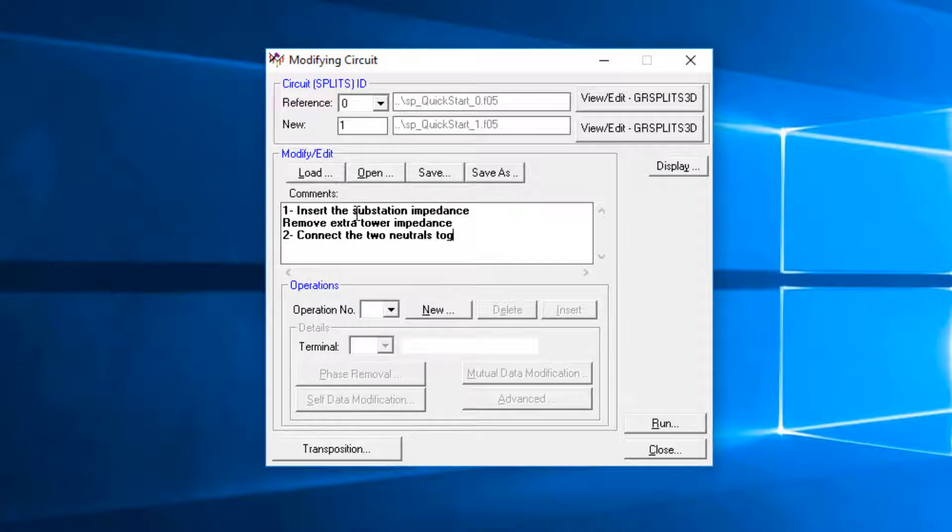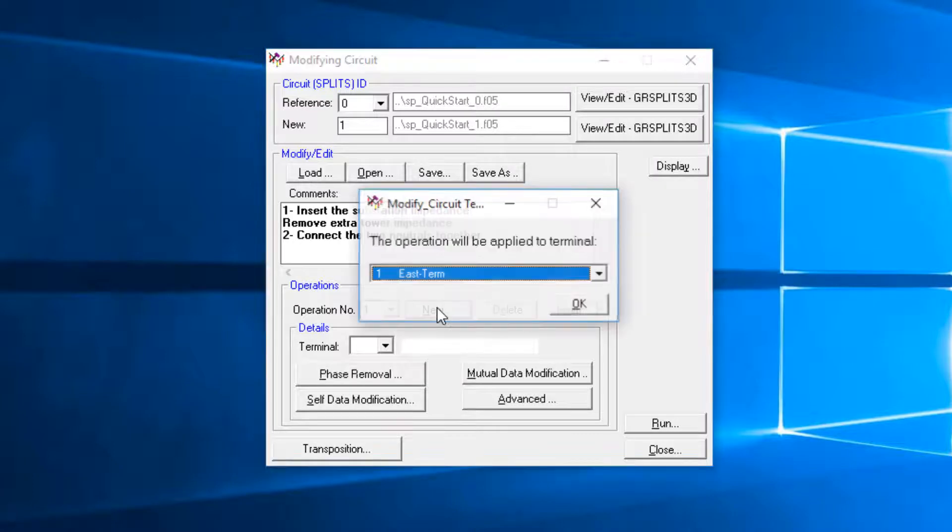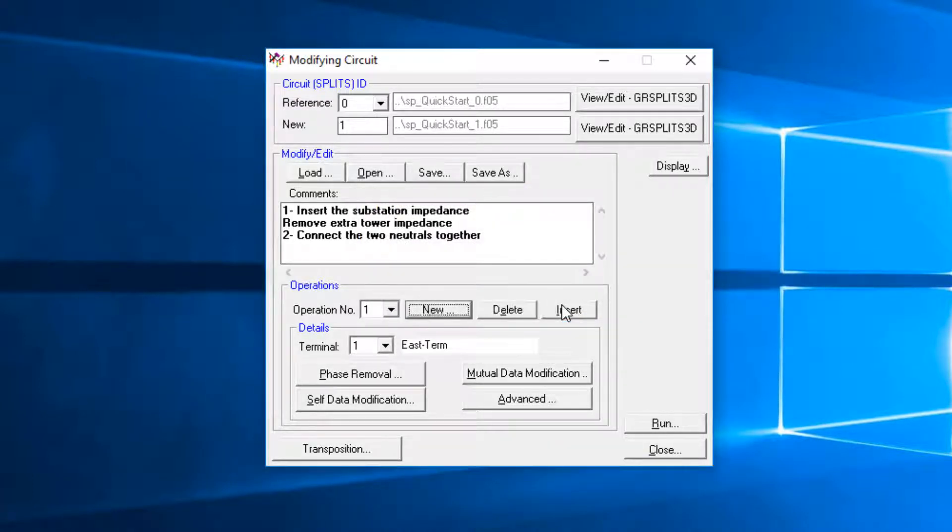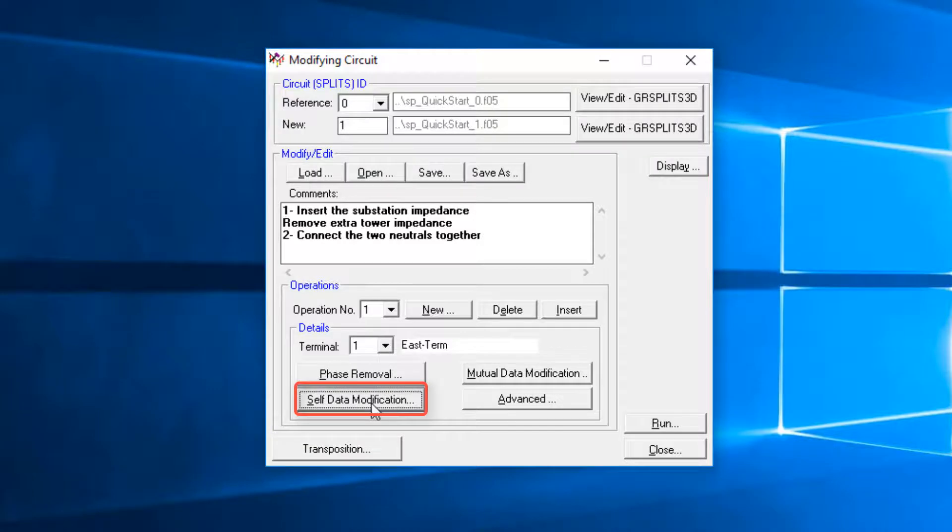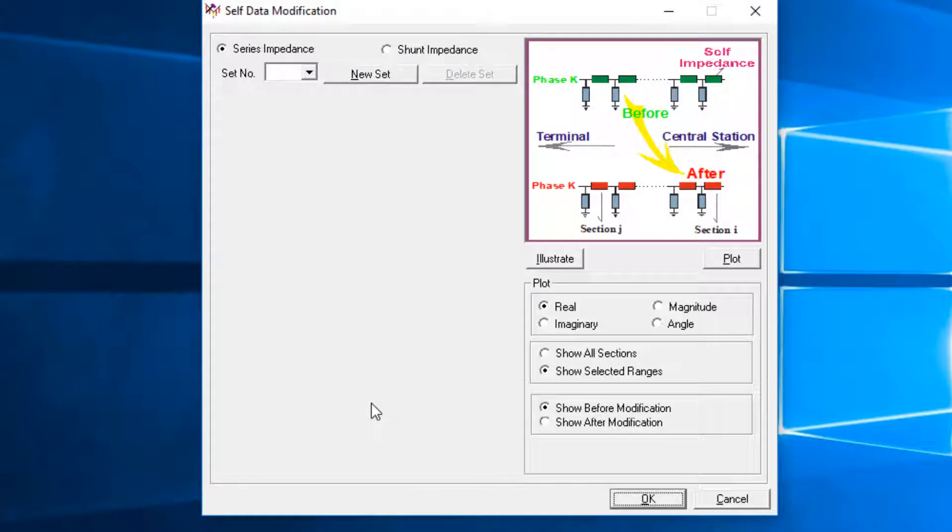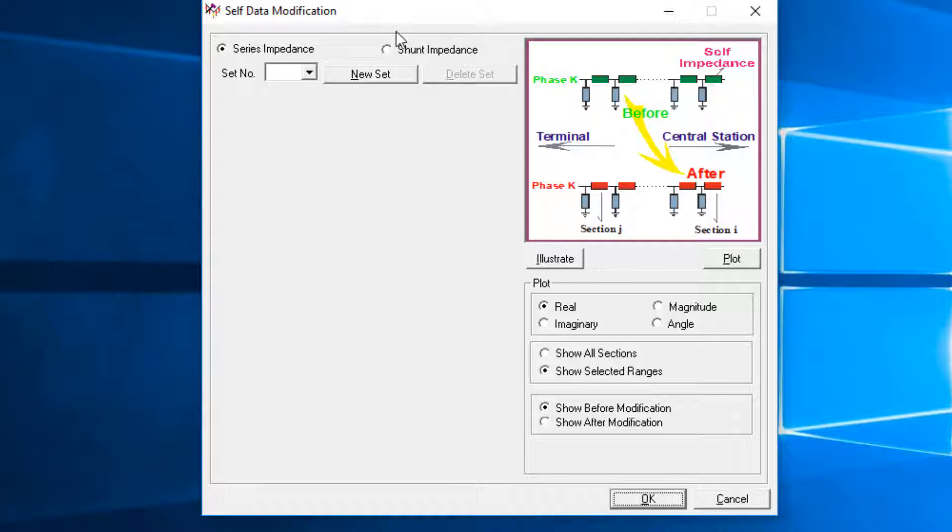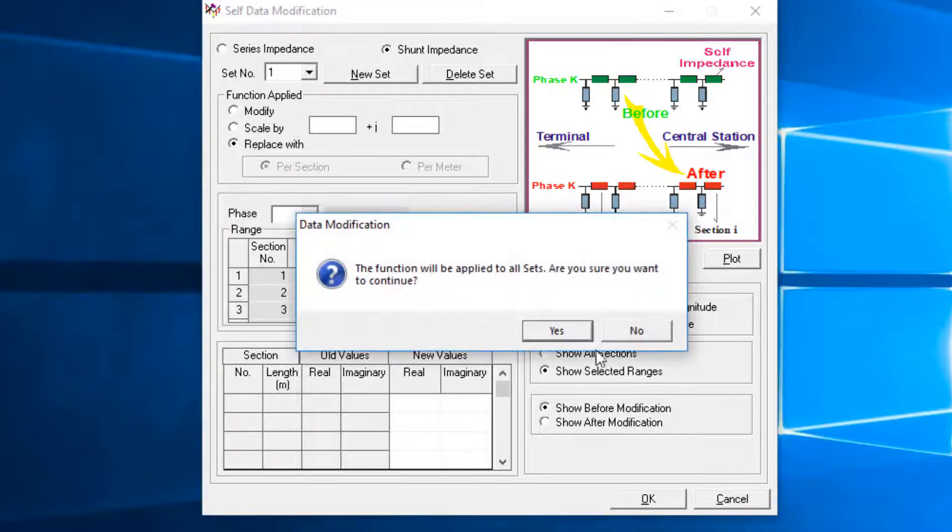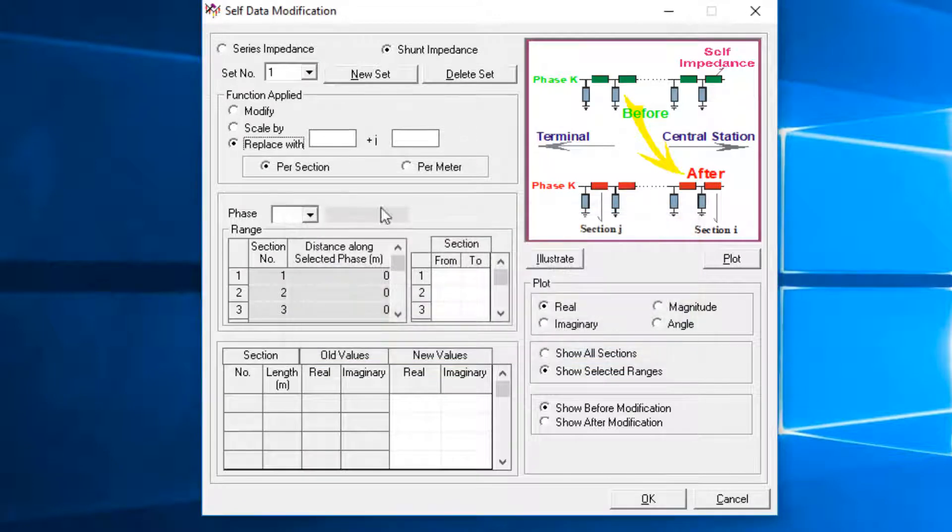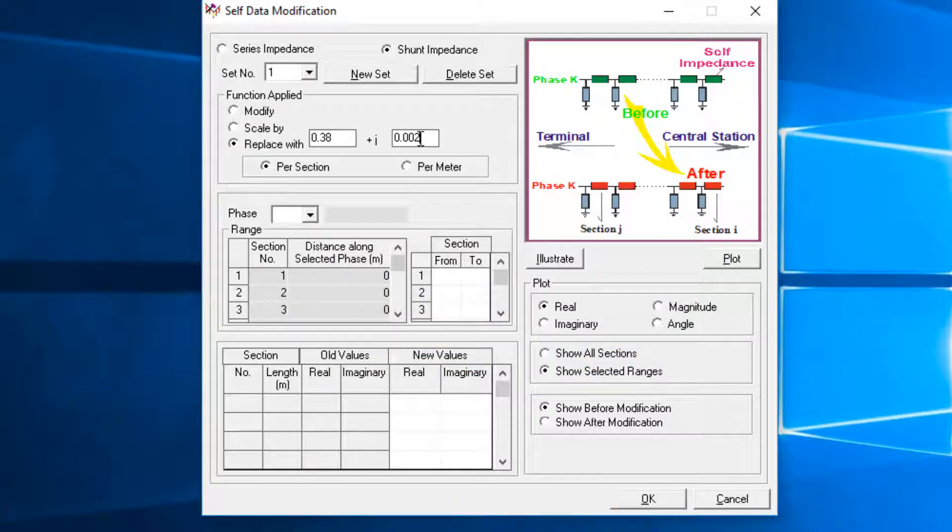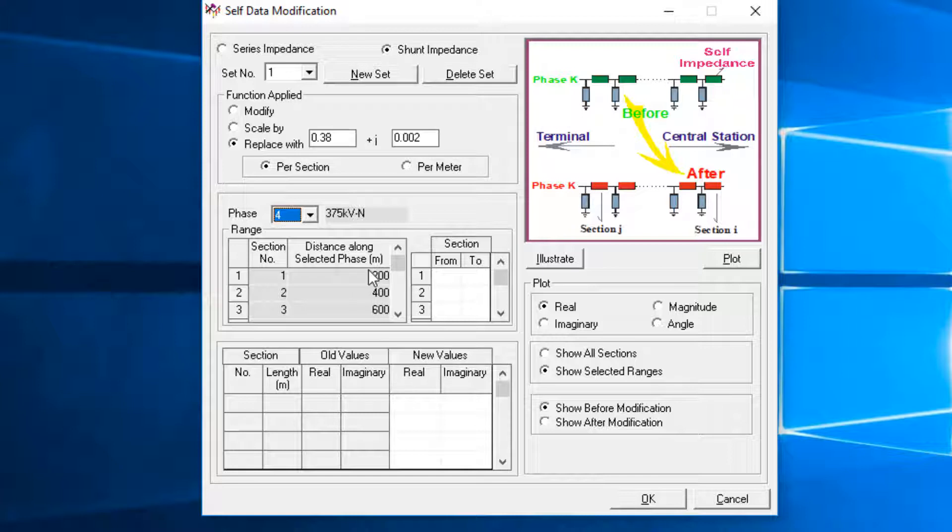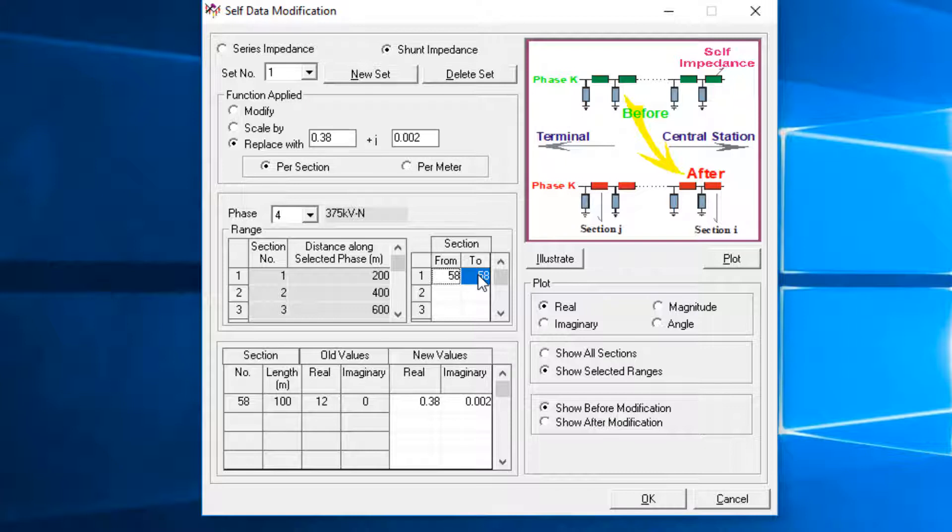Then click on the New button to start defining a new operation. Select the target terminal. Click the Self Data Modification button. Operation 1 is defined by using the Shunt Impedance option. Click on the New Set. Choose Replace With option and enter the new impedance value. Choose Phase 4, which is 375 kV neutral, and enter section from 58 to 58. The substation is added in the new circuit. This will replace the 375-line tower impedance with the substation impedance.